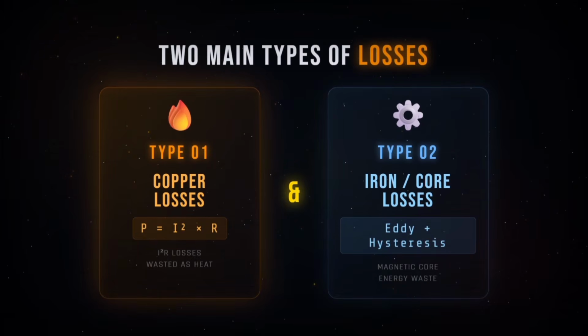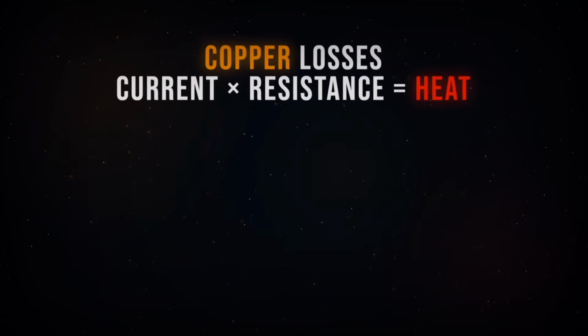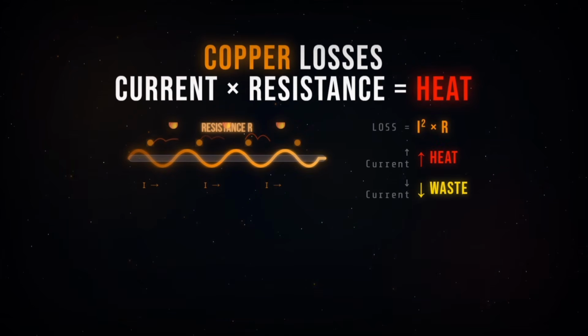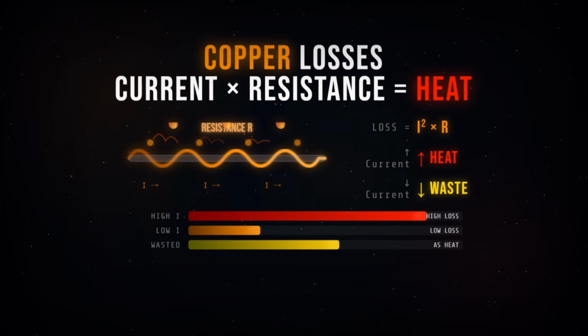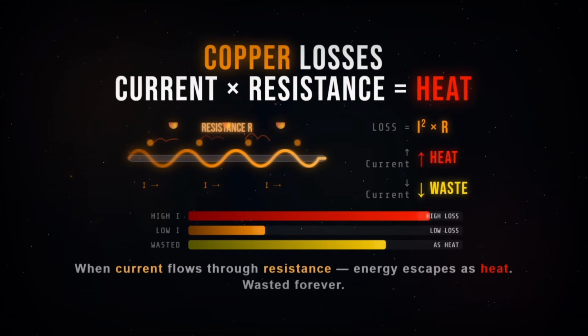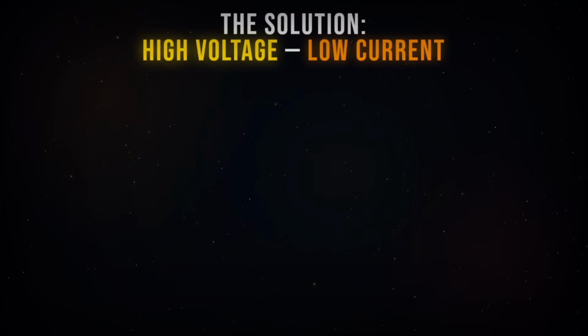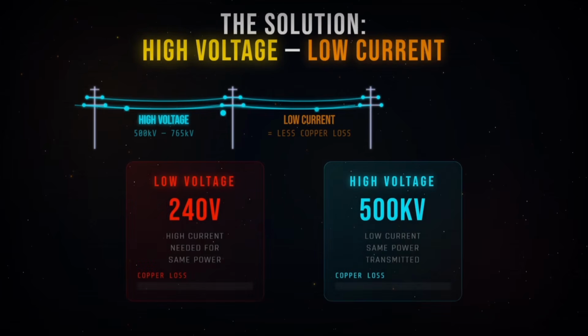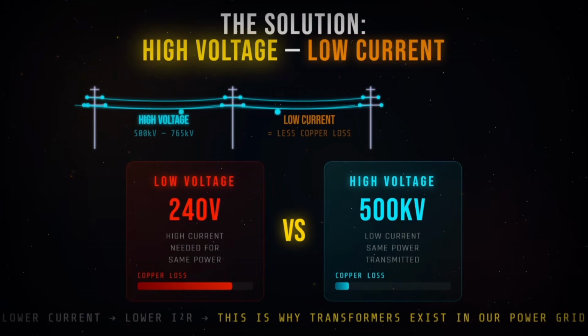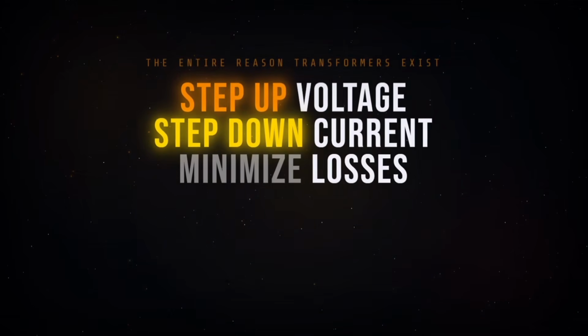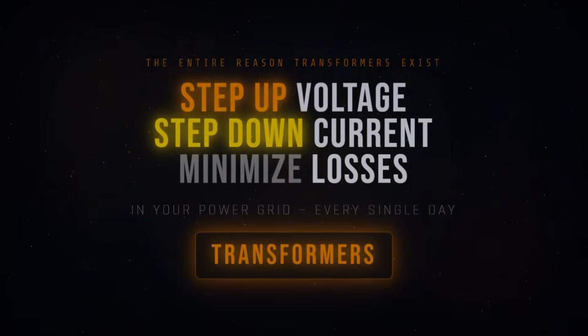First, copper losses, also called I squared R losses. The wire coils have resistance, and when current flows through resistance, heat is generated. That heat is wasted energy. This is why high-voltage transmission lines carry electricity at very high voltage and very low current. Lower current means lower copper losses. This is the entire reason transformers exist in our power grid.